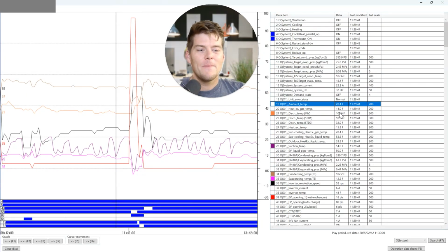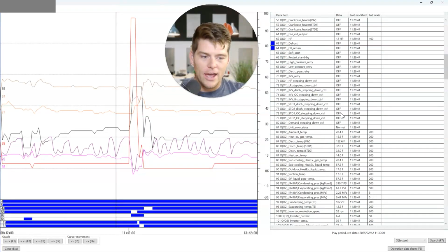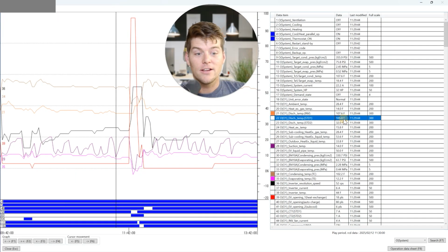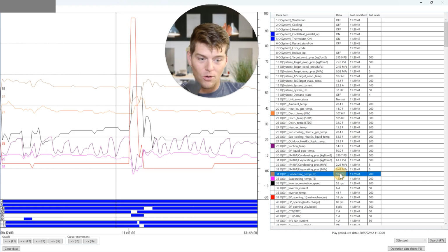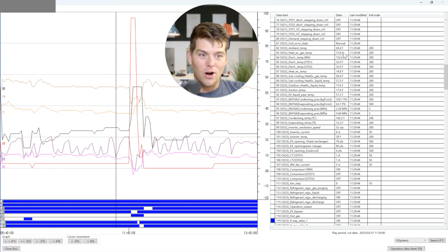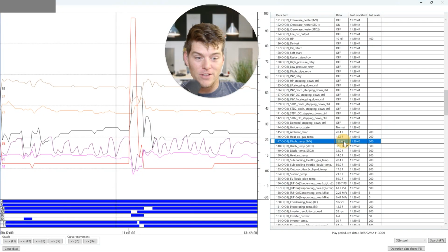Here we go. Discharge temperatures. All compressors are running right now. And let's start. Master module, discharge temperature, 107. Saturated temperature, 105. Really low. That's actually a 3-degree discharge superheat. Okay, what about my other modules? Well, I've got 152 here, and I've got 152 here.